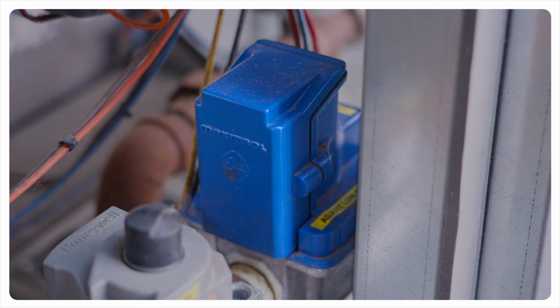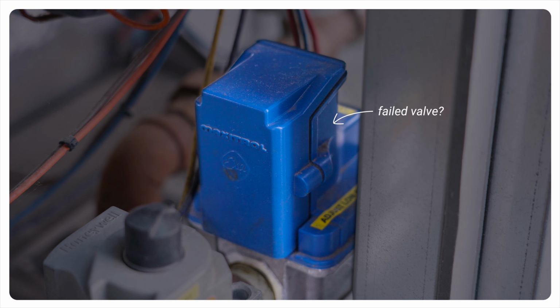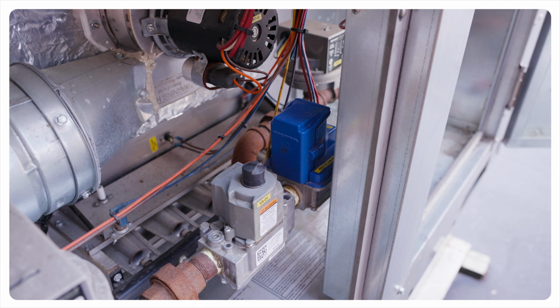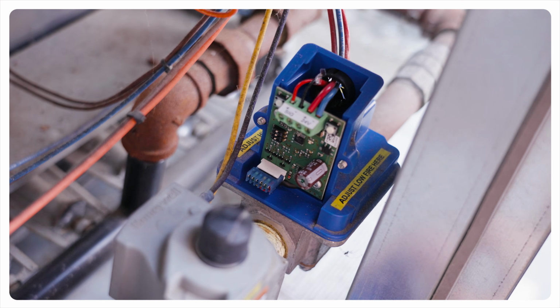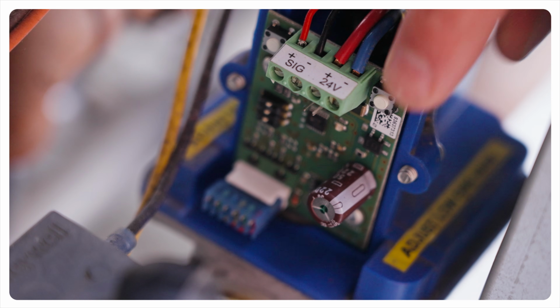So we knew it was one of two things. Either the gas valve itself, the modulating gas valve, had failed, or it just wasn't set properly. And when we sent our tech out there, they were able to come out with that valve in hand ready to go. But it turned out that all they had to do was just program that low fire setting.